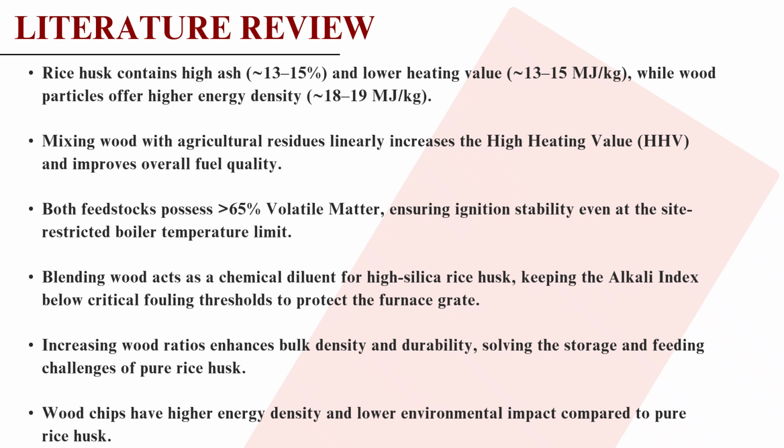Critically, for our boiler, both wood and husk have over 65% of volatile material. This ensures that the fire stays stable even at our restricted boiler temperature limits.